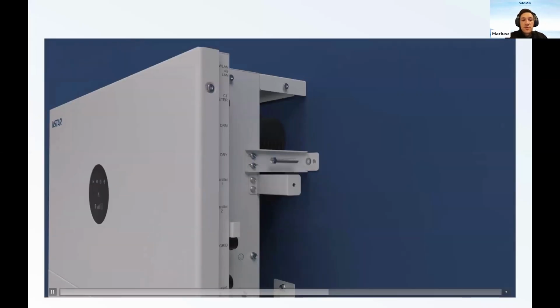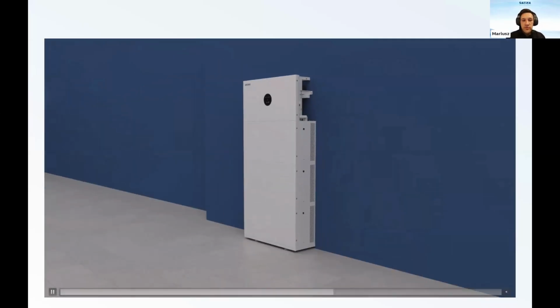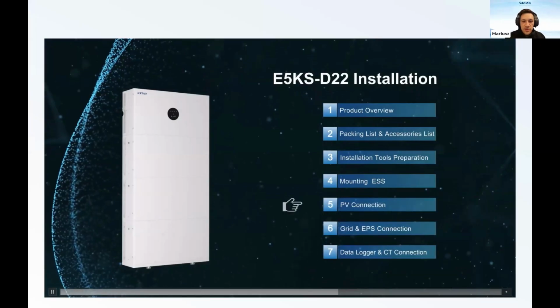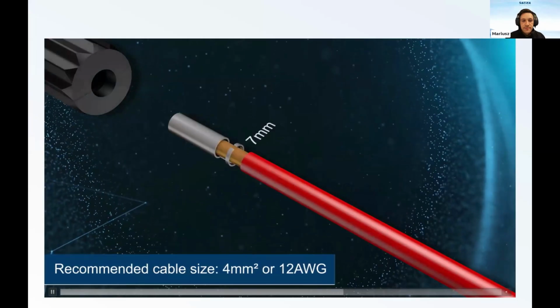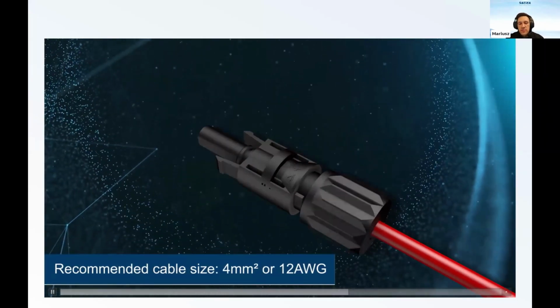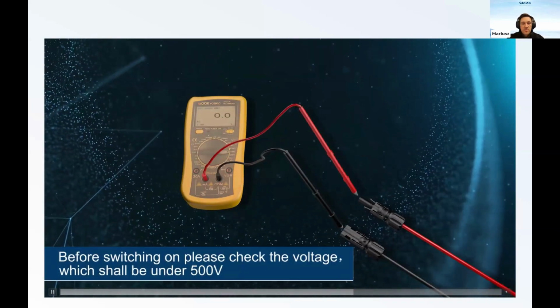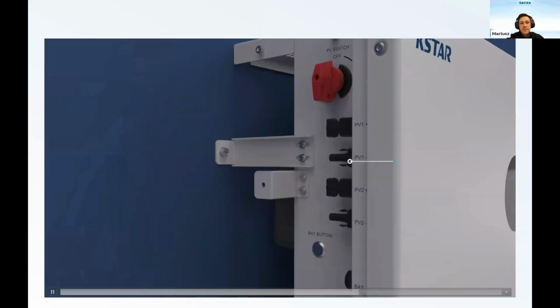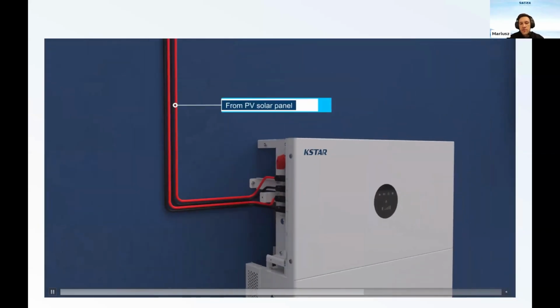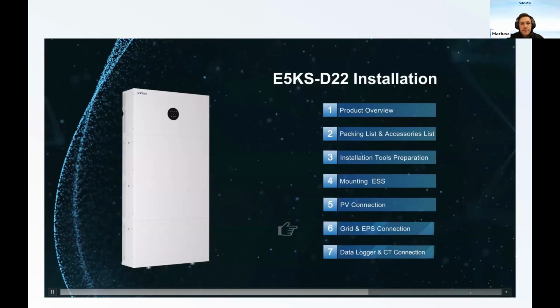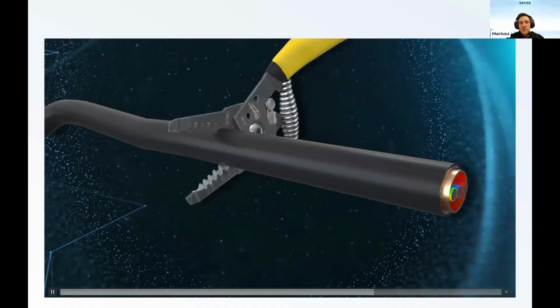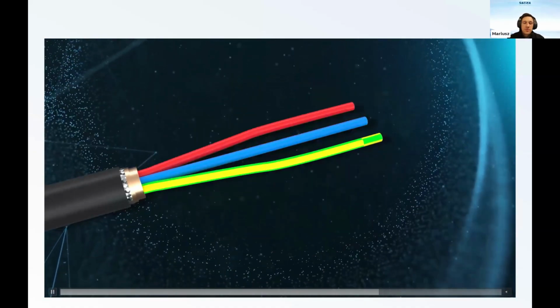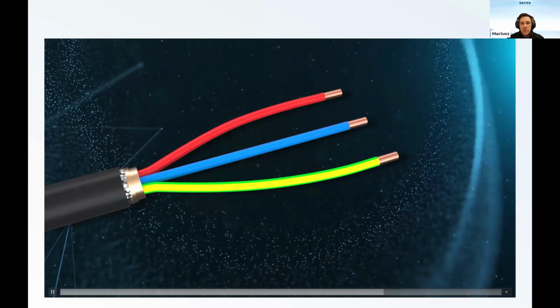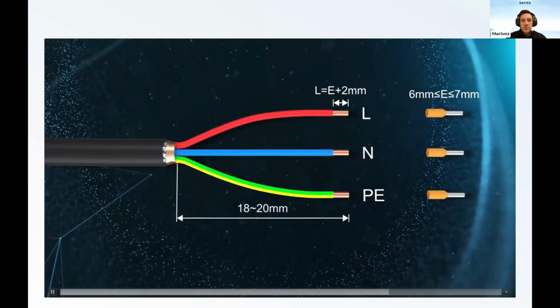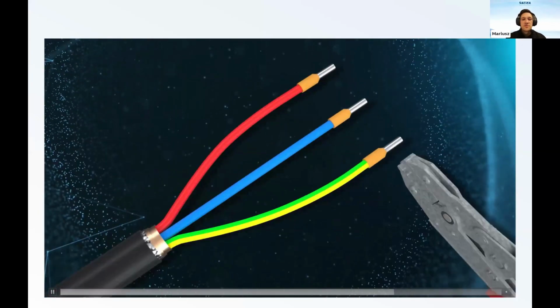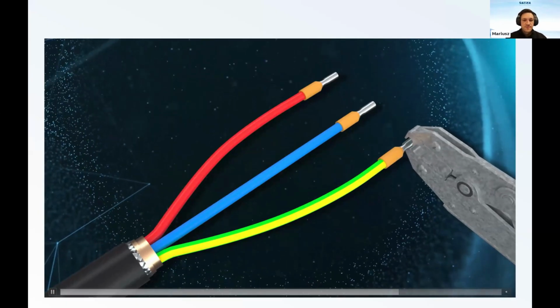Once everything is fixed to the wall, we can proceed with the connection of the wiring, like the PV modules and the communication, the grid and EPS connection, and so on. We can use 4 square millimeters or 6 square millimeters, depending on your personal installation requirements. And we have 2 MPPT inputs, high amperage. What is important, we have 2 inputs, 1 input and 1 output. The grid is an input-output terminal. The backup is only an output terminal, so be aware, just do not miss it. Do not connect the grid into the backup. The system will not work properly.